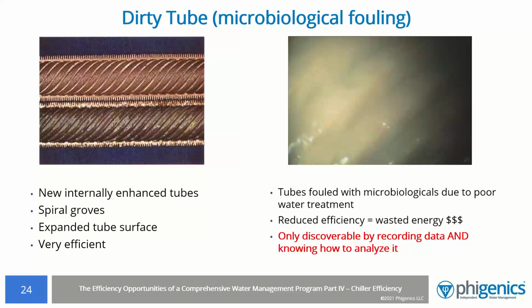And one thing that you need to understand is with internally enhanced tubes, how they're cleaned is important. The right process, the right method. You have to use the right kind of brush, two-direction brushing, and I think Mike is going to go through that in a little bit more detail. But there's a right process and a wrong process to clean these tubes. Make sure that whether you're cleaning them or your contractor's cleaning them, they're following the right process for cleaning internally enhanced tubes. And you can identify these problems, obviously, with a good logging process. A good logging method will tell you if, in fact, you've got significant fouling. Okay, next, Mike, back to you.